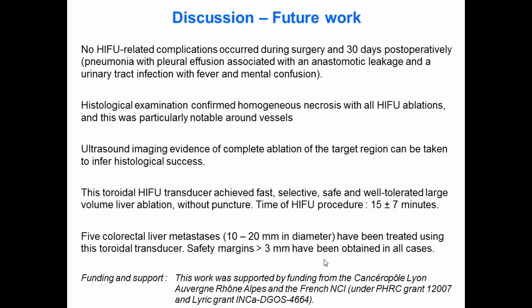Well, I have a question about the first time. How did you set the particular patients for the imaging, by imaging or by the predetermined target? How do you determine the exposure time? The exposure time is defined according to the depth and the size of the tumor. So we have several exposure parameters, and we can set the volume of ablation from 2 centimeters in diameter up to 5 centimeters in diameter, and we set that according to preoperative ultrasound imaging.